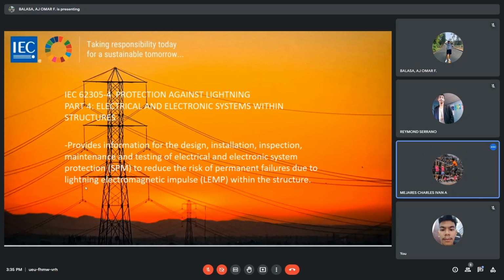IEC 62305 Part 4: Electrical and electronic systems within structures. It provides information for the design, installation, inspection, maintenance, and testing of electrical and electronic system protection, or SPM, to reduce the risk of permanent failures due to lightning electromagnetic impulse, or LEMP, within the structures. This standard does not cover protection against electromagnetic interference due to lightning, which may cause malfunctioning of internal systems. Also, this standard provides guidelines for cooperation between the designer of the electrical and electronic systems and the designer of the protection measures in an attempt to achieve optimum protection effectiveness.